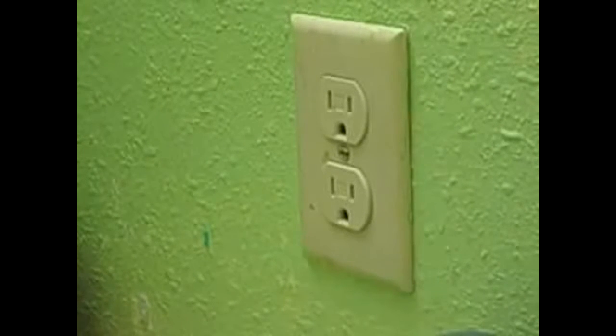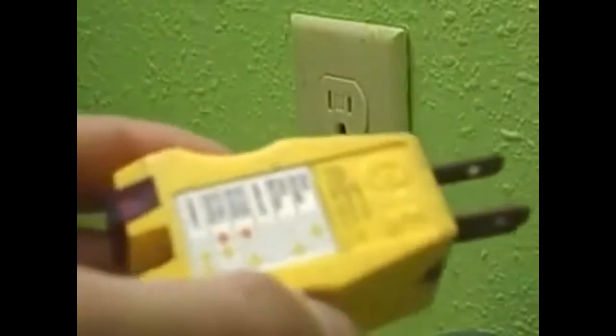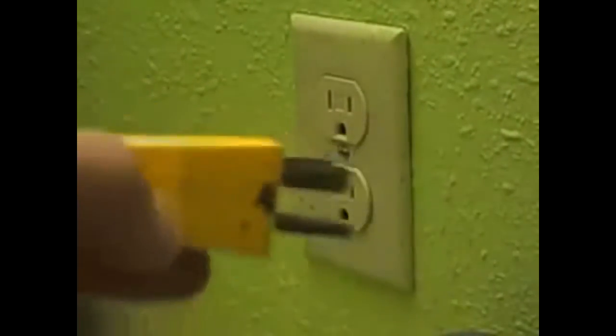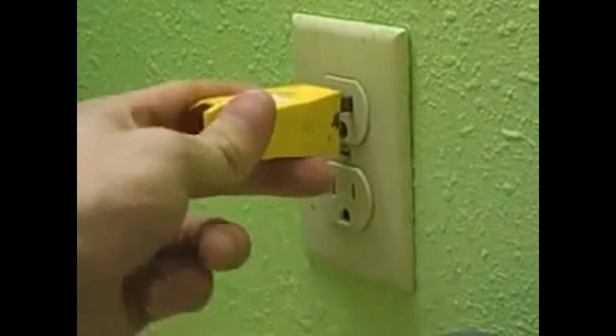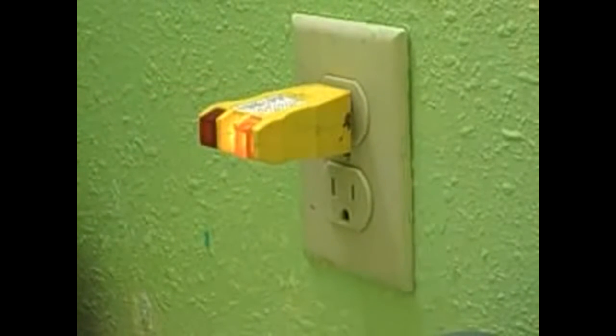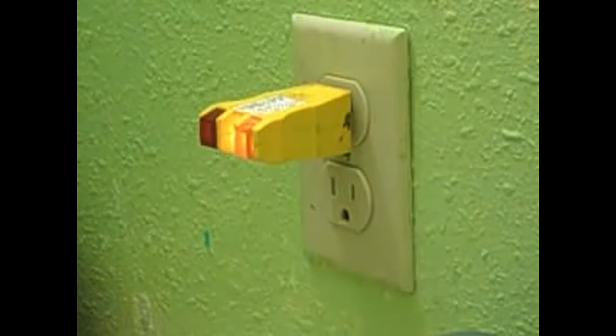Next, turn the power back on at the circuit breaker and take your polarity tester, which has labels on top telling you the sequence the lights will light up in any event. If you did everything correctly in wiring it up, the two yellow lights should light up when you plug it into the electrical outlet. If it's any other order, that means you got it wrong. So let's check ours out. Two yellow lights have lit up, which means our electrical outlet is installed correctly.